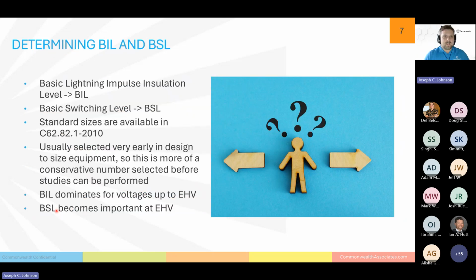So how do we actually classify these insulations and the levels there? Well, that's BIL and BSL. So BIL is the basic lightning impulse insulation level. That's actually BLIIL. I have no idea who came up with that acronym, but it looks nice. BSL is the basic switching level. So basic lightning level, that is for lightning events, and basic switching level, that's for switching events. There's standard sizes based on your voltage. These are not necessarily something you come in and pick your own voltage. There's standard classes. These involve separation distances, clearances. They're built in with all of those considerations for that voltage level into the BIL and BSL.